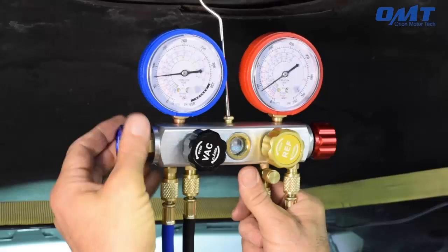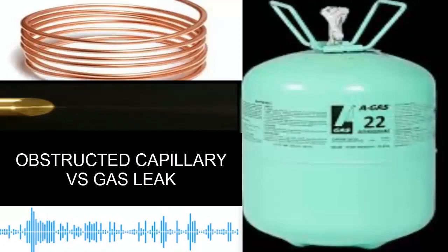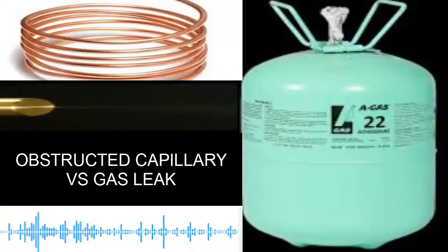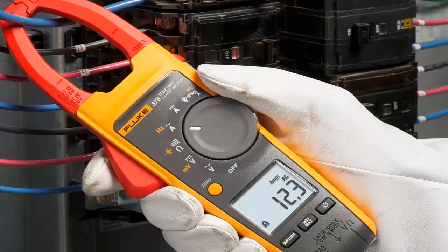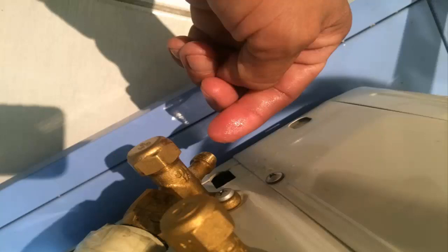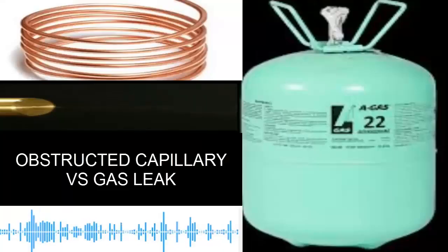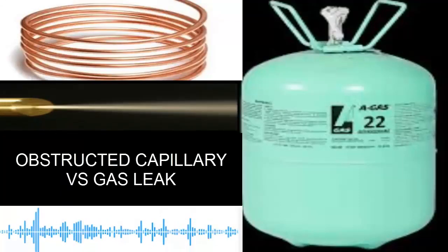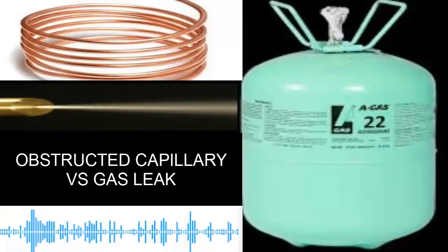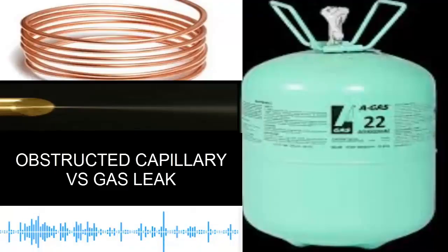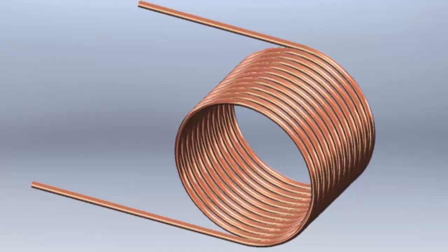B. In addition, another indicator of a lack of refrigerant in the equipment is that the compressor's amperage should be lower than normal since the system, with less refrigerant, requires less electrical energy due to compressing less gas. C. By verifying the mandatory presence of the two previous symptoms, observe the capillary tube with the equipment turned on. A dry and warm capillary is a sign of a healthy capillary and a confirmation of a lack of refrigerant.